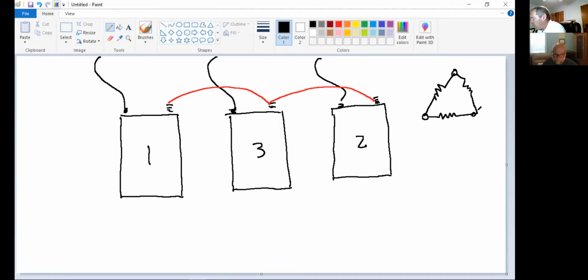Simply put, when you have ferroresonance and I pull off any one of these transformers in this situation, it doesn't matter the combination, as soon as I pull off the first transformer, the other two transformers are going to have a voltage spike. The voltage spike is from load trying to be compensated by the other two transformers. Voltage is going to try to compensate for the amount of amperage that was lost by this transformer. In order for me to compensate for the load, what does voltage have to do?